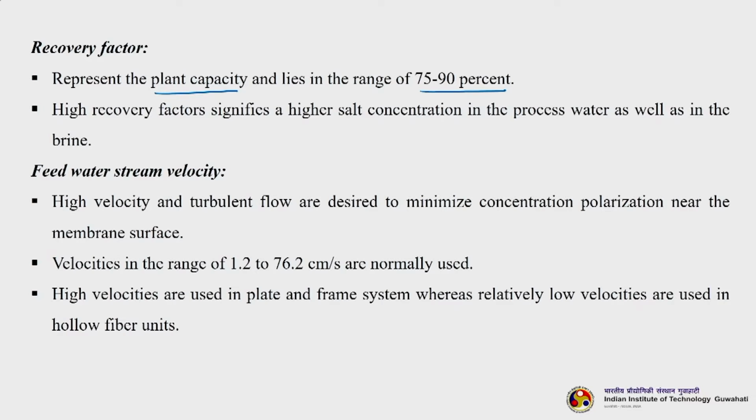Then the next parameter is feed water stream velocity. High velocity and turbulent flow are desired to minimize concentration polarization, as I just told on the earlier slide. Velocities in the range of 1.2 to 76.2 centimeters per second are normally used. High velocities are used in plate and frame systems, whereas relatively low velocities are used in hollow fiber systems.